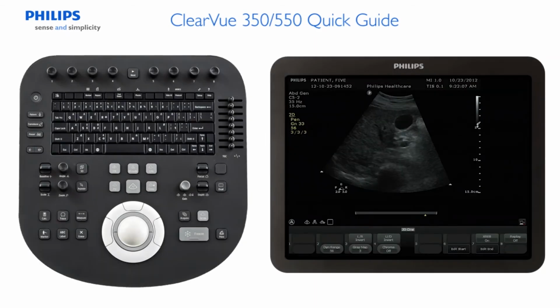The following section will describe the tools used for measurements. In the lower left portion of the control panel are keys for measurements, calculations, and trace. Pressing the Measure key begins an unlabeled measurement in any mode. Use the right and left trackball buttons to toggle between calipers. Press the middle trackball button to set the measurement. Please note that these measurements will not populate into the report.